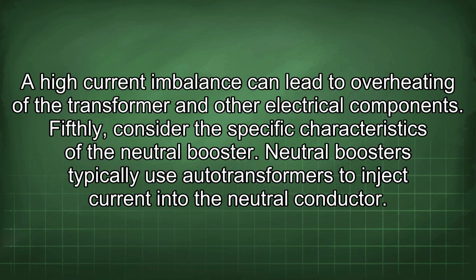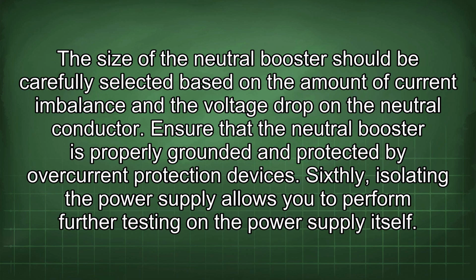Fifthly, consider the specific characteristics of the neutral booster. Neutral boosters typically use autotransformers to inject current into the neutral conductor. The size of the neutral booster should be carefully selected based on the amount of current imbalance and the voltage drop on the neutral conductor. Ensure that the neutral booster is properly grounded and protected by overcurrent protection devices.